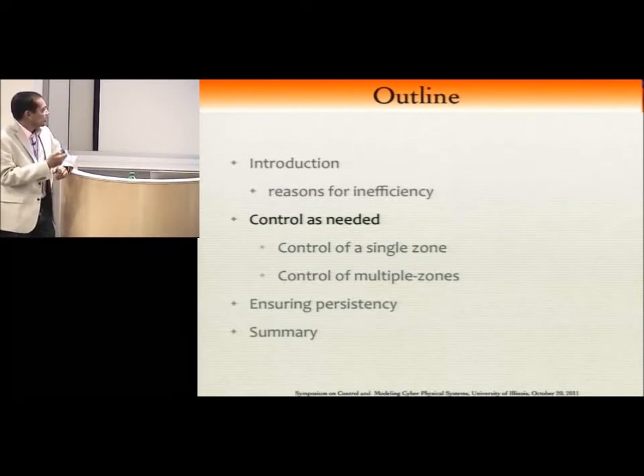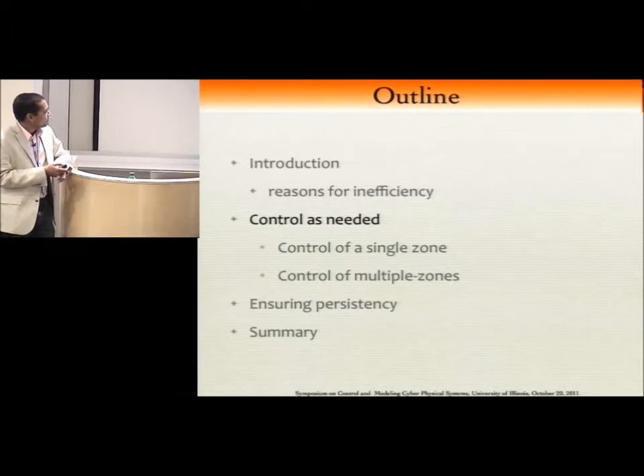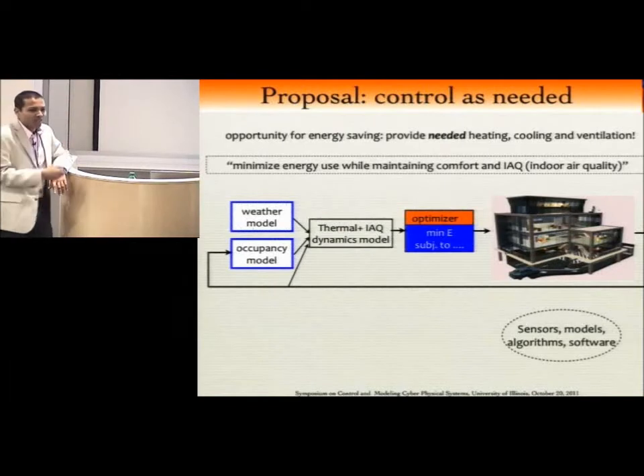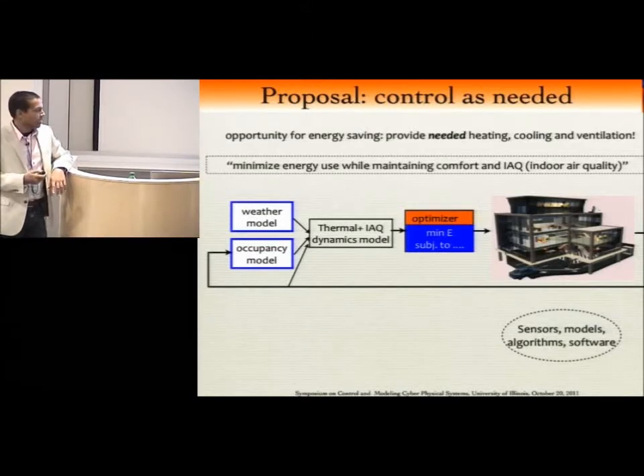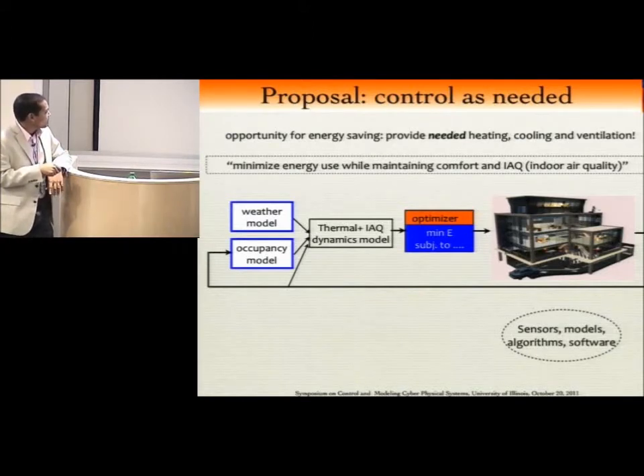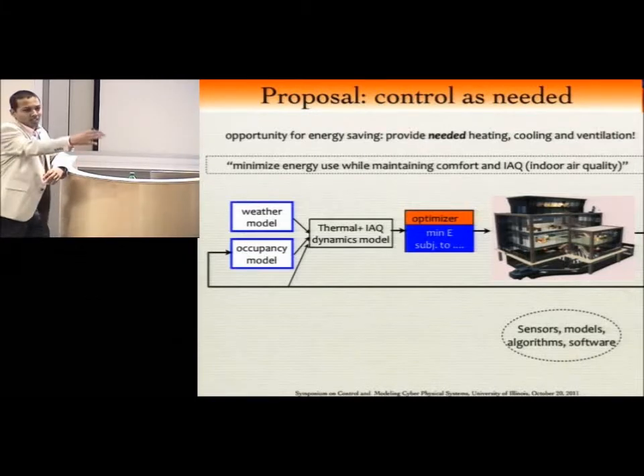So you can, of course, being a controls person, this is how I think about it, you may think about it differently. If somebody poses this problem to me, I'll say let's apply optimal control. Let's predict how things are going to happen based on models for weather, models for how occupants are going to change, how occupancy levels, meaning number of people in a zone or building, are going to change. I'll construct some models for the thermal dynamics, etc. I'll feed all this into a big optimizer which will determine what I should be doing from now till the next half hour, or now till the next 24 hours, or now till eternity if you can do that, so that it minimizes energy use subject to constraints, like temperature should be within some bounds, indoor air quality has to be maintained, humidity has to be maintained, etc.